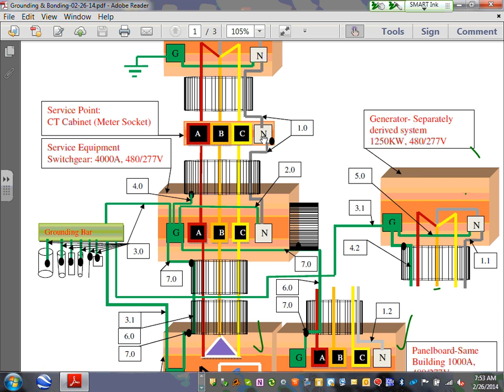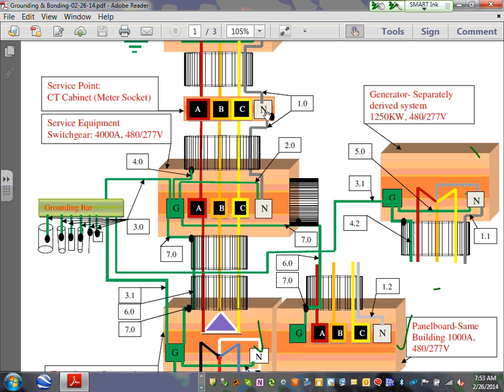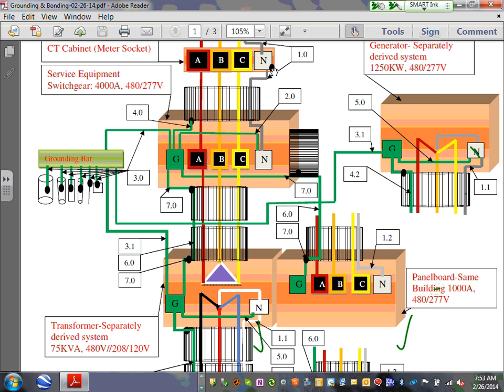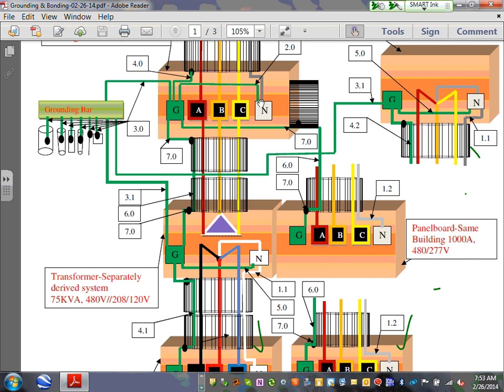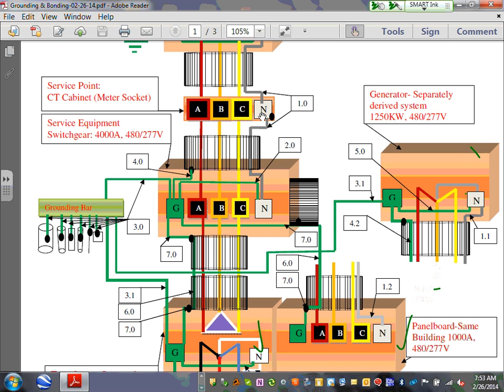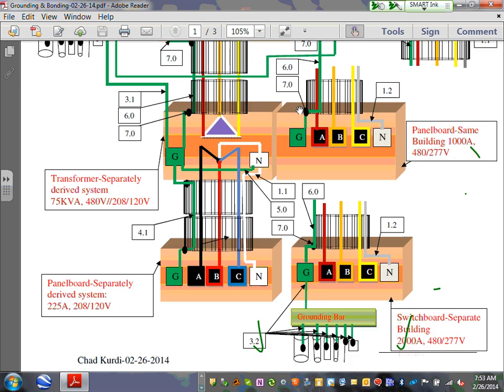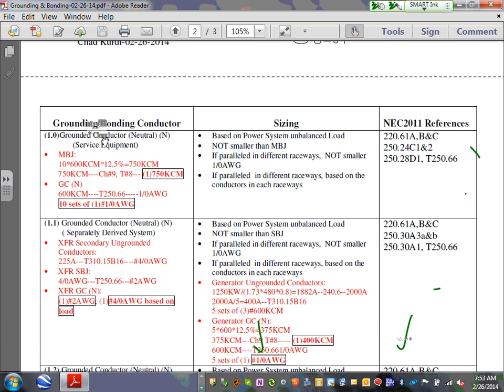Remember when we went to EMI? Isn't that what you guys saw? That CT cabinet? They tie it to the neutral, and they also bond the box with that neutral. They are allowed to bond the box with the neutral. And then they bring it into the switchgear, the main panel. Everybody understand the 1.0? It's called the grounded conductor. If you go right here, 1.0 says grounded conductor, neutral, service equipment. By the way, on the test and the final, this should be with you, because I don't know if anybody can do the calculation without having the sheet in front of you. It's just so involved. So 1.0, grounded conductor, neutral at the service.